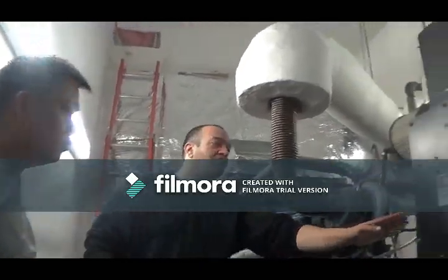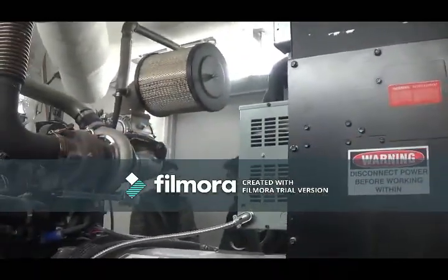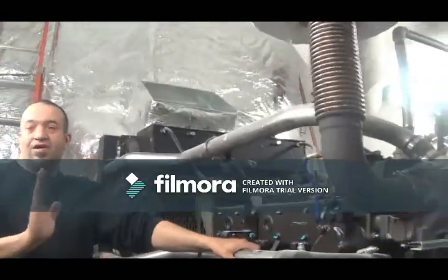This is your charger related to the battery, okay? You want to see the voltage. You see where the gauge is? Anywhere between 28 and just below 30 is good. So the lowest one is below 30. If you see it above 30, usually there's something wrong. It's either overcharging. So like 28, 26, it's good. Even if it touches just barely 30, you're okay.